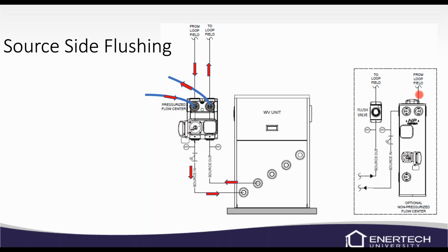So we're not flushing here and here, I'm sorry. So we don't flush through this non-pressurized flow center or through the unit at that point. We're just going to flush the loop field. Never flush through a non-pressurized flow center.